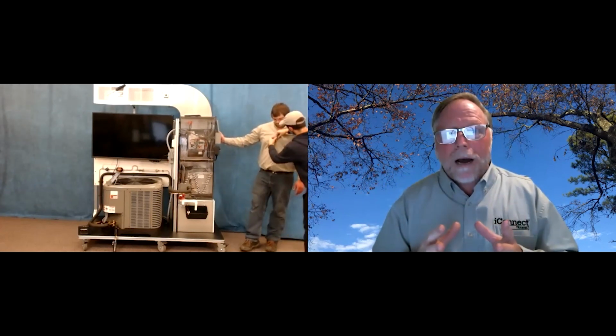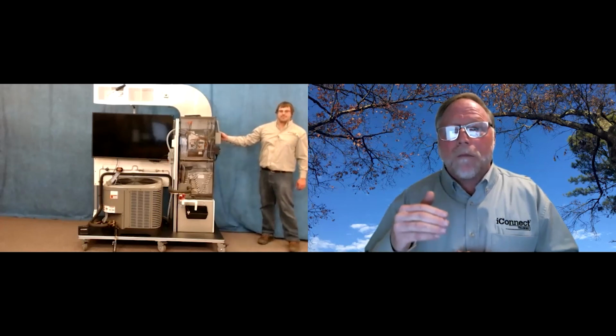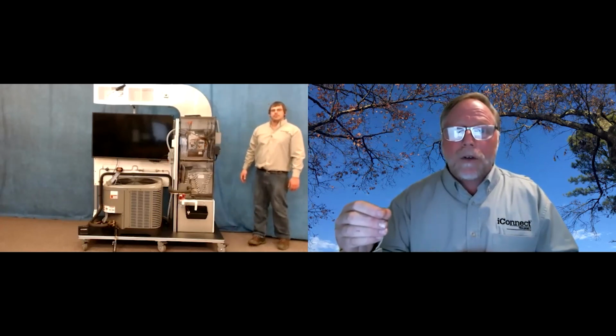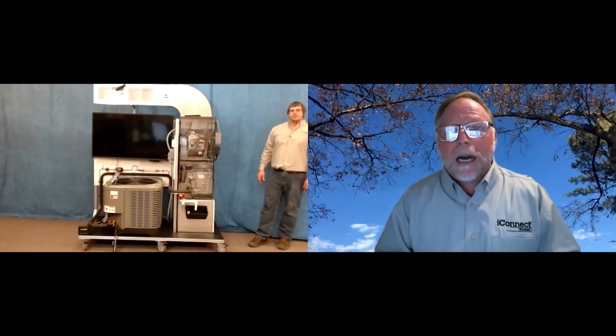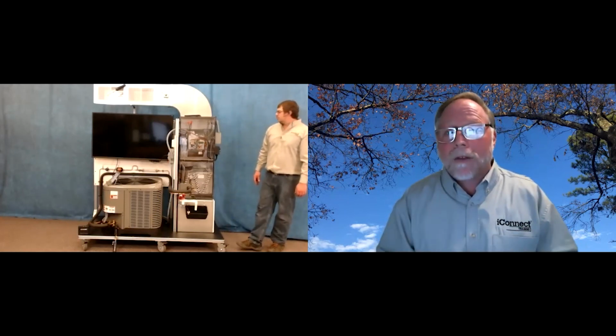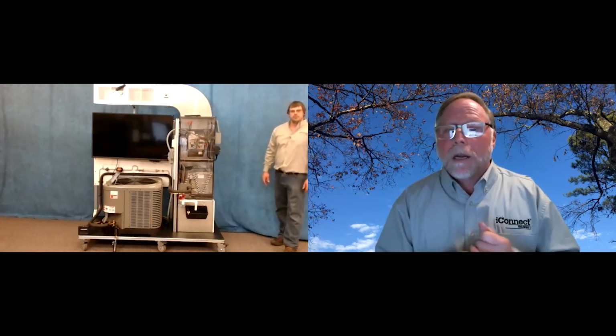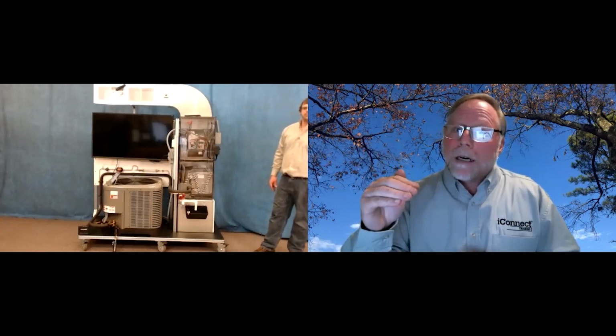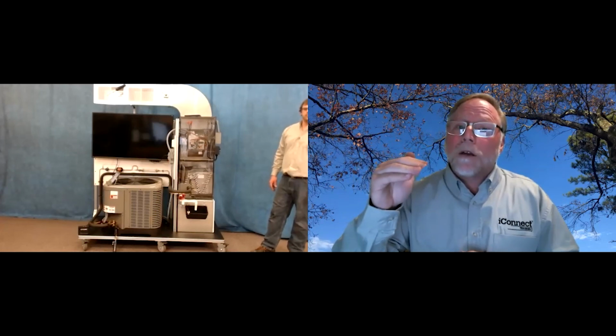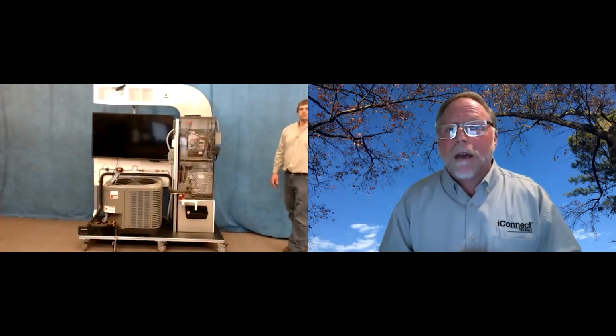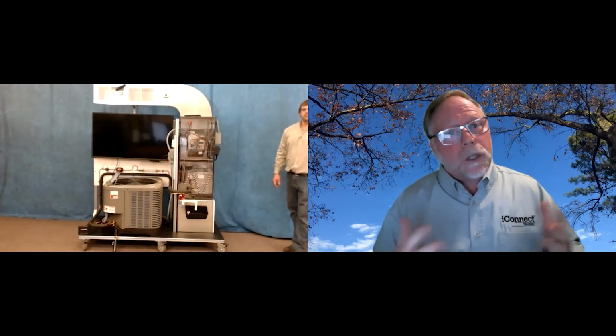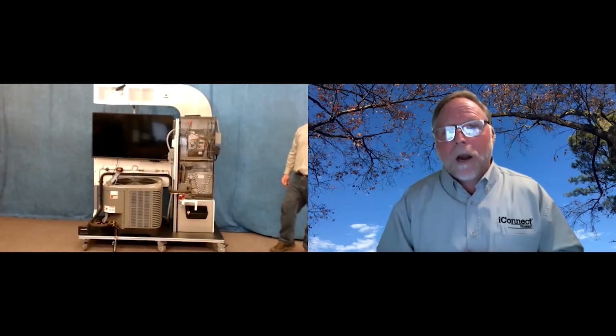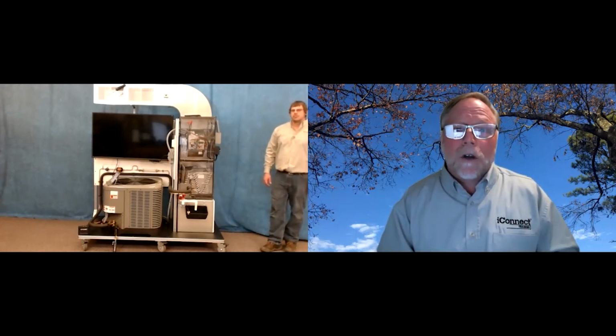And then the last thing we were talking about was the effects of the motor, and different motors react differently to restrictions. And we talked about that PSC motor. And now you can see how airflow affects it. You do a quick amp draw on it and see for yourself before you pull out anything. If it's moving 100% airflow, then the PSC motor will be pulling 100% of its amp draw. But if it's moving less air, then it'll be pulling less current through the amp meter, and the student can quickly see, they can do an airflow check or an airflow idea just by pulling the amp draw on the motor before they pull out all the other airflow instruments. And that's our 6 lessons for the TU 406C, the iConnect training.